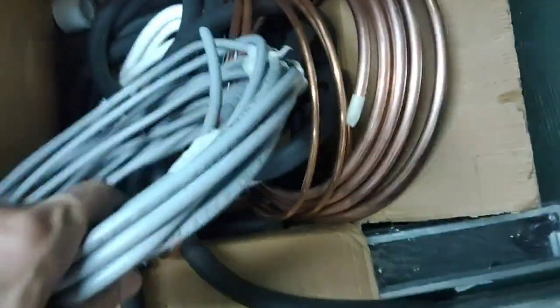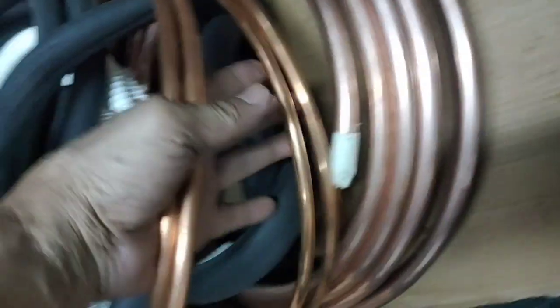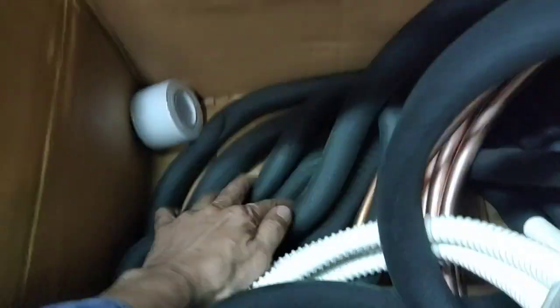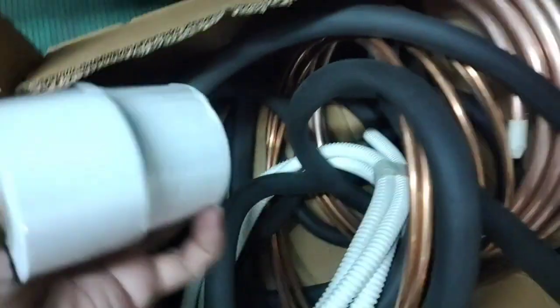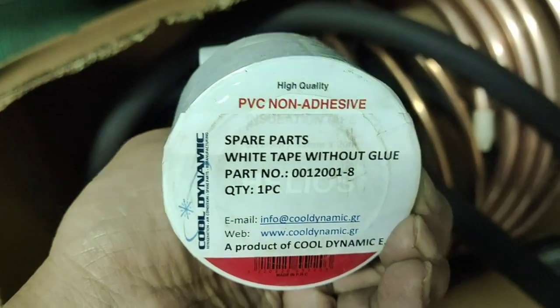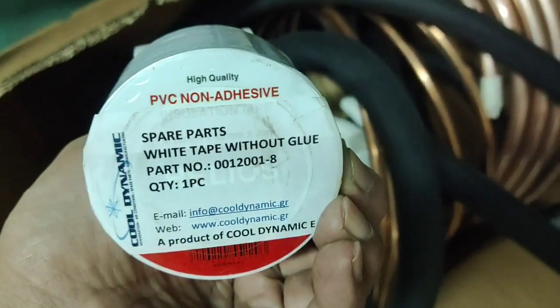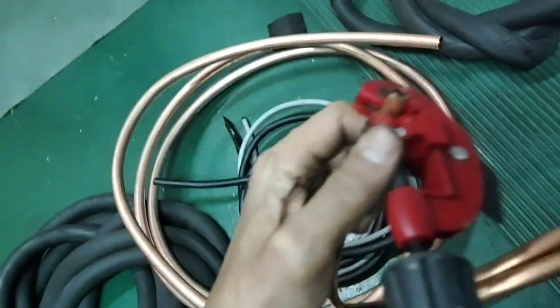Now we are checking this. These are the brackets for the evaporator. These are the cables to be used for the connection to the evaporator and condenser. This is the high side, this is the low side pipe, the insulators, and this is the drain pipe. This corrugated one is the drain pipe. This one is for the insulation, and we have to look for the tape when all pipes and cables are installed. So we can put this tape. It's PVC non-adhesive tape, white tape without glue.